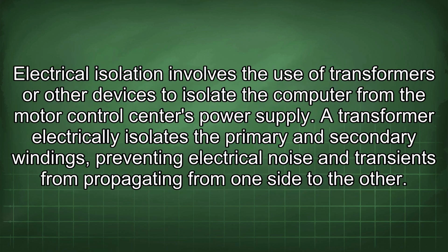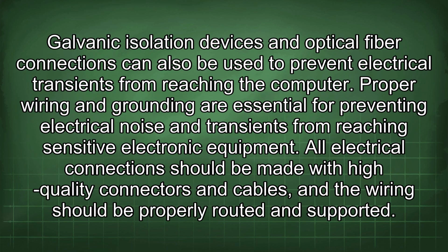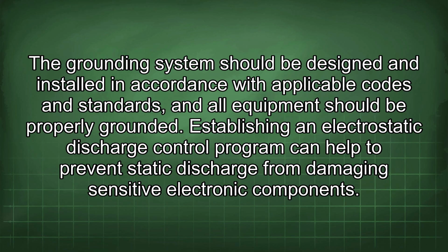Power conditioners can also be used to filter out electrical noise and surges, providing a cleaner and more stable power supply. Electrical isolation involves the use of transformers or other devices to isolate the computer from the motor control center's power supply. A transformer electrically isolates the primary and secondary windings, preventing electrical noise and transients from propagating from one side to the other. Galvanic isolation devices and optical fiber connections can also be used to prevent electrical transients from reaching the computer. Proper wiring and grounding are essential for preventing electrical noise and transients from reaching sensitive electronic equipment. All electrical connections should be made with high-quality connectors and cables, and the wiring should be properly routed and supported.